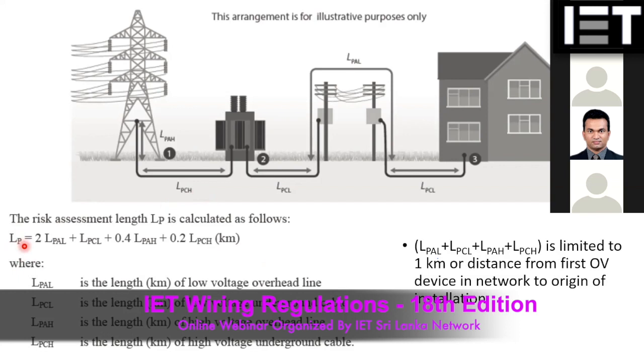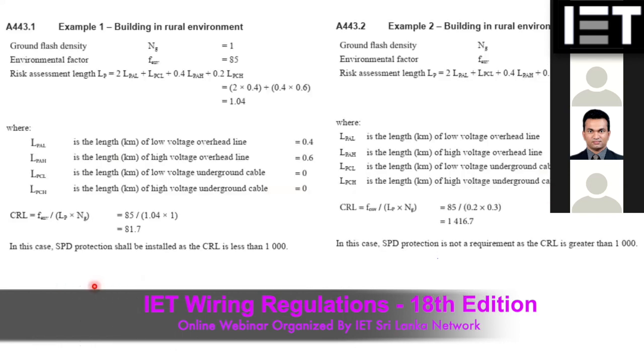The other one is NG. NG is the lightning flash density in a particular location. That also you can get from the meteorology department maps: the lightning flash density in different locations in Sri Lanka. Then you can calculate the risk level. There are examples given in the new regulation, so that you can calculate these NG values and the environmental factor. It's a very simple calculation. Anybody can do it without any problem, so that we can check whether we need SPD, or surge protective devices, or not.